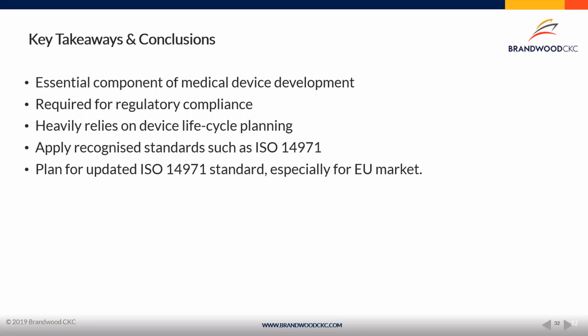When you get to the point where you've done design and development, you should have a pretty well established risk management file. Doesn't mean it's the end. So not only in your risk report are you identifying where you're going to collect production and post-production risks and risk inputs, but having that be a continuous process so that it feeds back into your risk management file, and you get a good understanding that not only did you assess them correctly initially, but also that you're doing the right thing and that anything that's coming up that you may not have seen is available and being appropriately addressed.